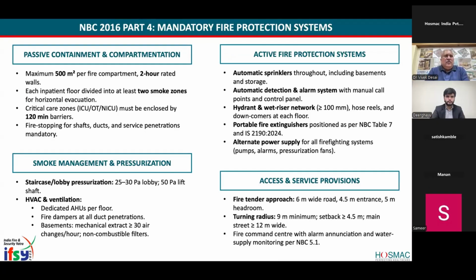In terms of compartmentation, 500 square meters per fire compartment. The inpatient floor should be divided into at least 2 smoke zones for horizontal evacuation. Critical care zones should be enclosed by a 120-minute barrier. Fire stopping for shaft ducts, we've already mentioned that. Smoke management, he just mentioned that, 25 Pascal to 50 Pascal in the lift shaft. HVAC and ventilation is one of the key criteria to fight fire in a proper way, and this should not go wrong, because most hospitals now are becoming centrally air conditioned, including those owned by the government. So all AIIMS are centrally air conditioned.